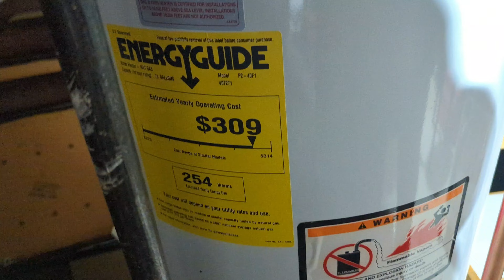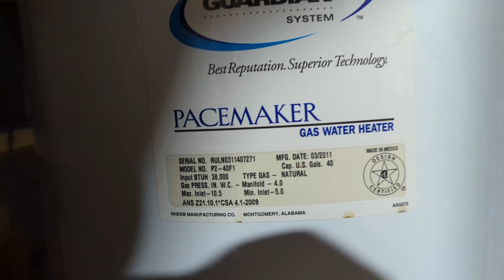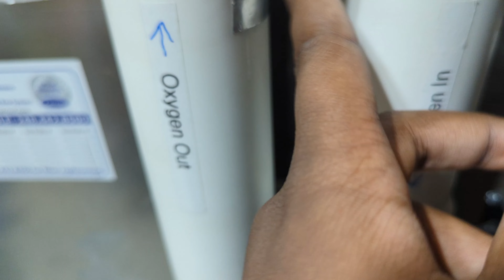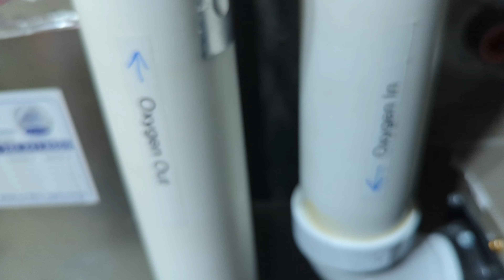This is a 73-gallon water heater. Actually, no. It's a 40-gallon water heater. You only need 38,000 BTUs for domestic hot water because this property's like 1,000 square feet. So you only need like a low amount of BTUs for a water heater and or boiler. You don't need that much BTUs. Now the condensing should be improved because I put the thing back on, so that should be much better. Plus this pipe, you could tell the air's just strictly going inward. This pipe is cold, this one's warm. You can't really tell the difference between them except for the fact that this is warmer than the other one. Now this test port wasn't sealed much, so I had to seal it myself. It's not even hot at all.